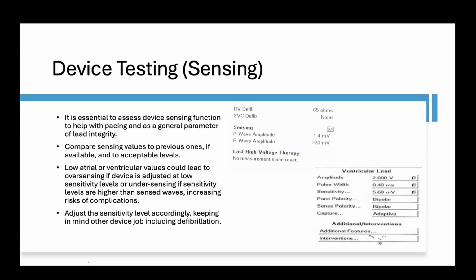and make sure these levels are acceptable. Low atrial or ventricular values could lead to over sensing if the device is adjusted at low sensitivity levels, or under sensing if they were programmed at high levels than sensed waves, and this increases the risks of complications as well. So you could see here on a Medtronic device, it sensed the P wave at 1.4 and the R wave about 20 or more than 20. And then based on the numbers that we see, we basically adjust the sensitivity level here. 5.6 a bit high, but then it depends.